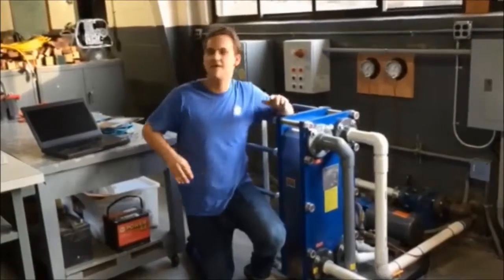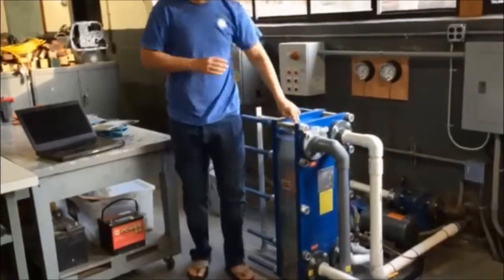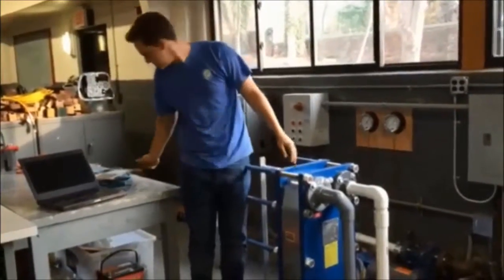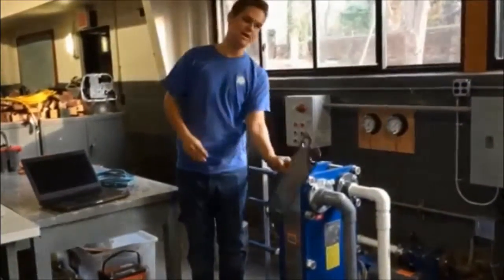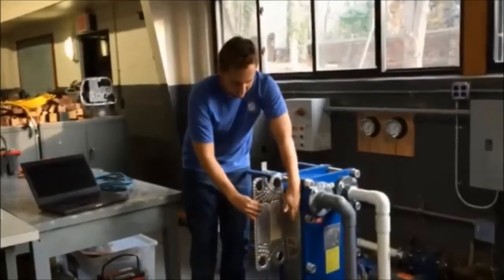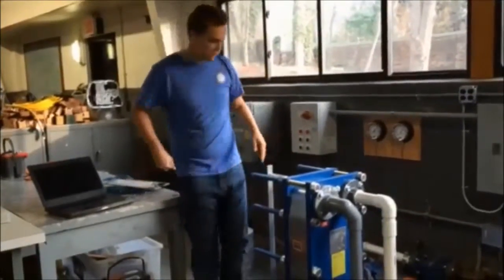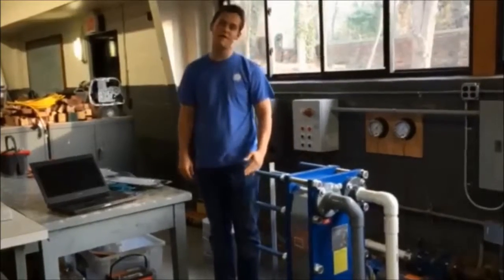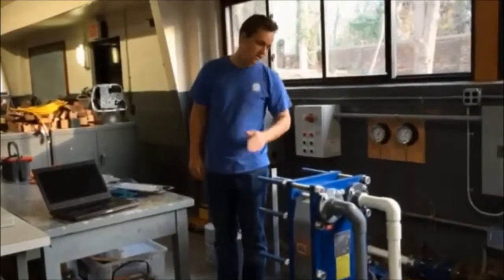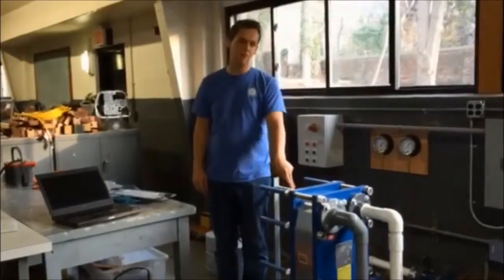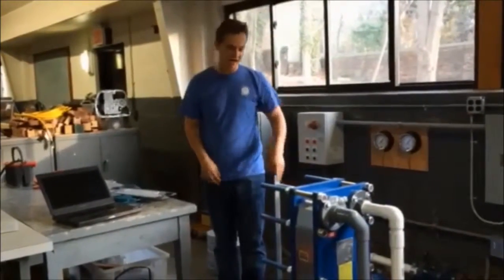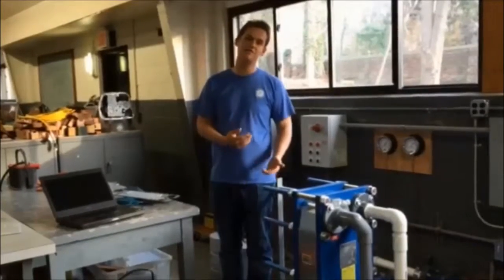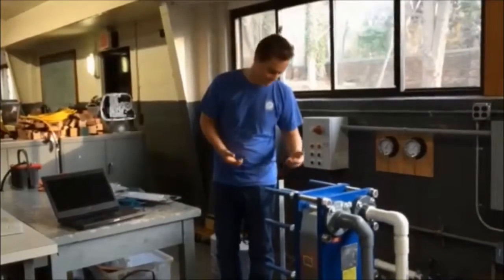Important features of the plate-type heat exchanger are the stack of plates located behind the shroud. We'll talk about those a little bit more, but the plates all look like this, and they're stacked together in this fashion. Through the heat exchanger, you can see these tightening holes, which are much longer than they need to be for the size of the heat exchanger. This is because you can take off these bolts, move the back of the plate back, and add or reduce plates as necessary. More plates obviously results in more heat exchange.